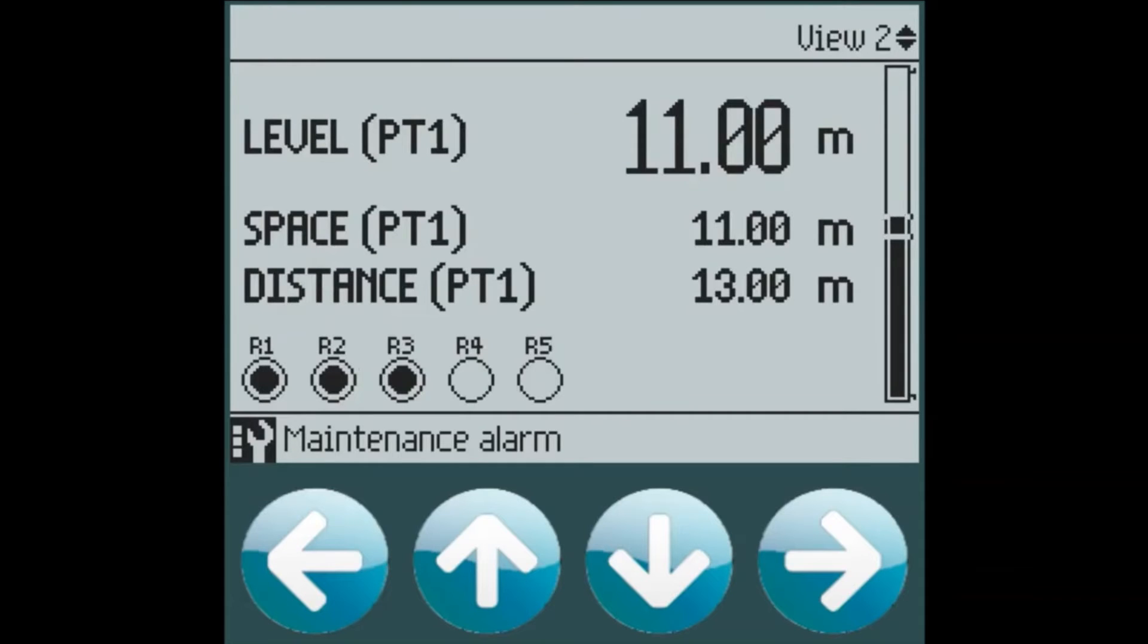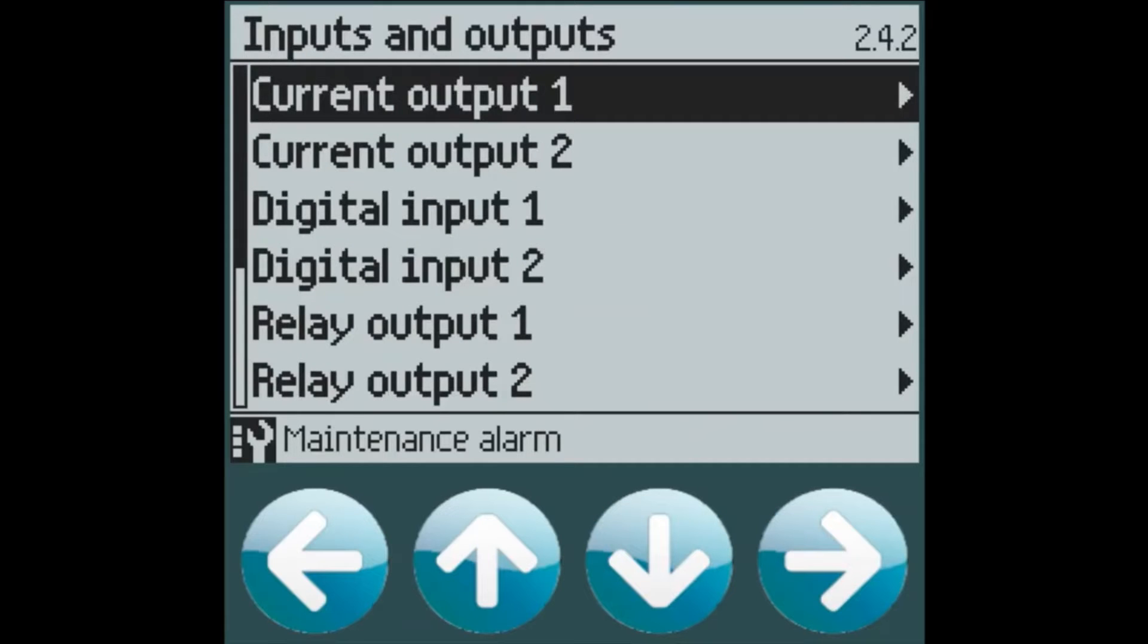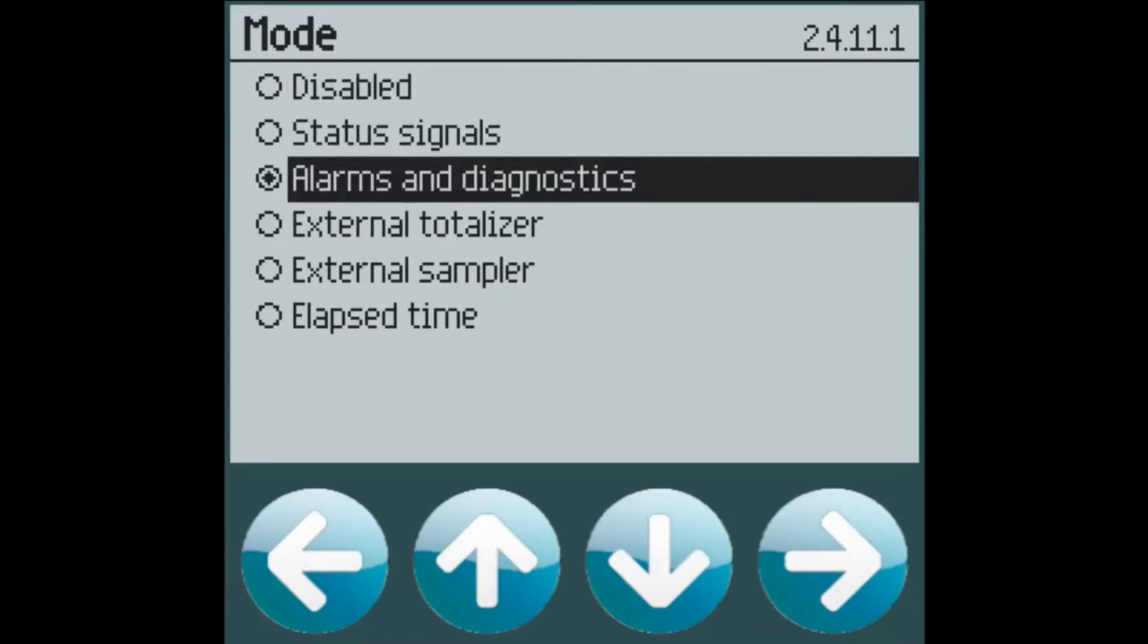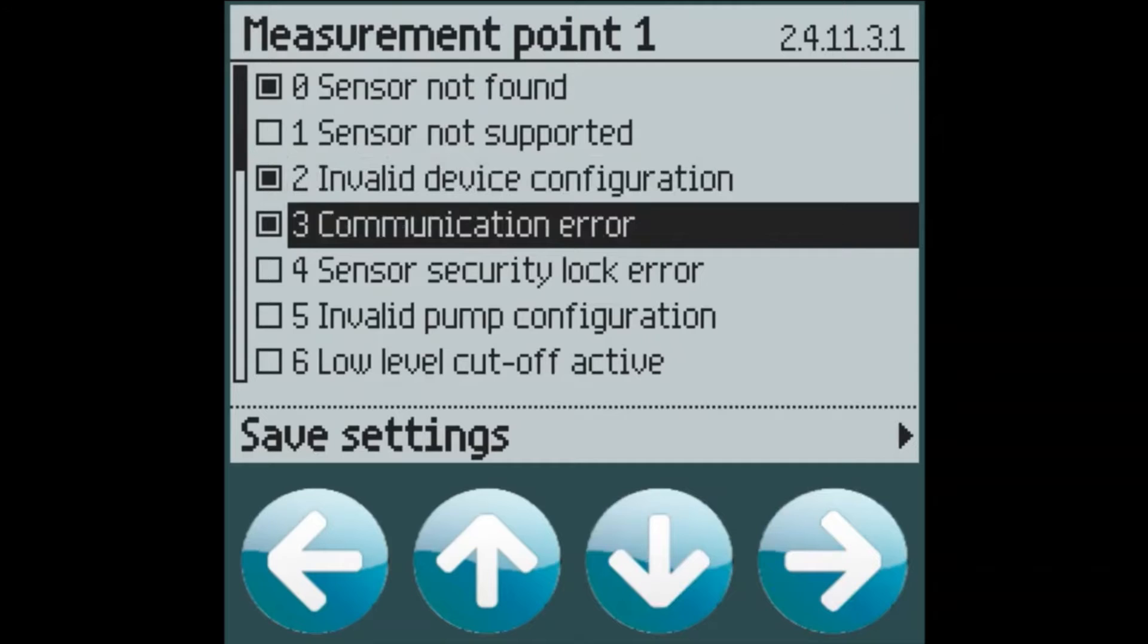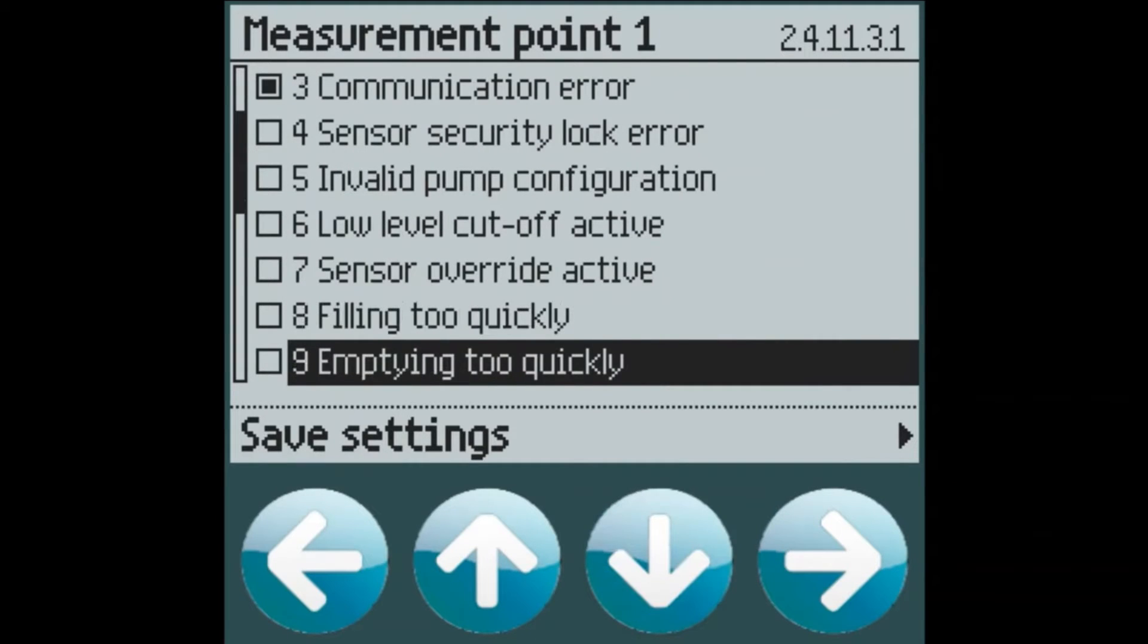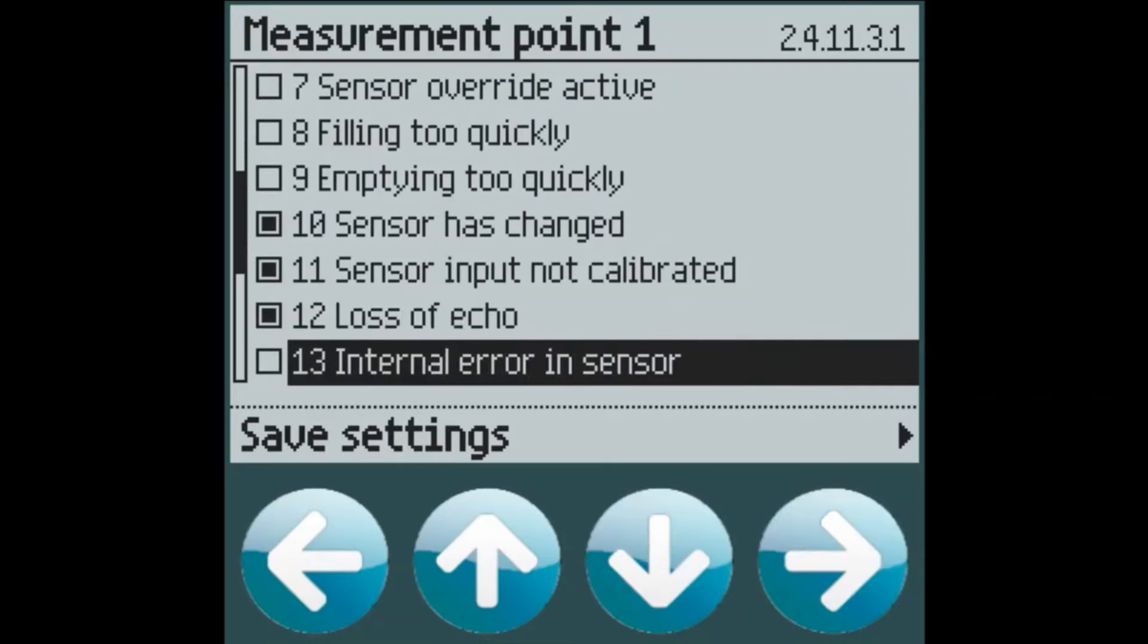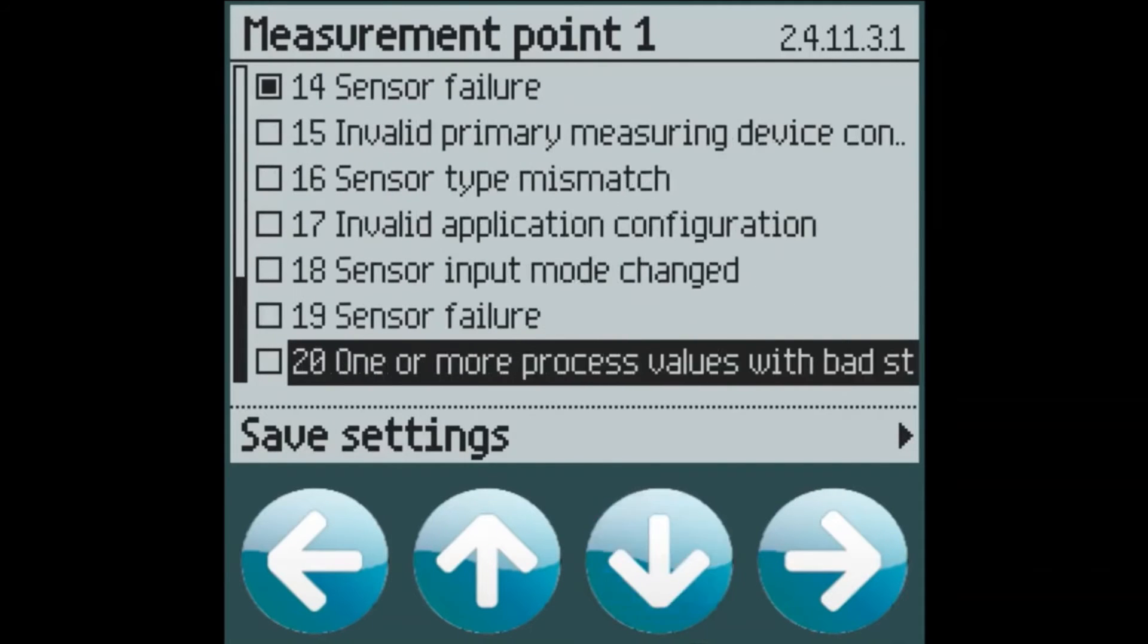We have now set our two alarms, 4 and 5. We can add a third alarm on relay 6 for our sensor diagnostics following the same steps. Under inputs and outputs and relay number 6, we can turn on alarms and diagnostics and select our sensor diagnostics. This will allow us to choose any of the sensor diagnostics which we wish to turn on the relay. Say sensor not found, invalid configuration or communication error. Sensor has changed, sensor not calibrated and definitely a loss of echo. Sensor failure and we can save our settings.